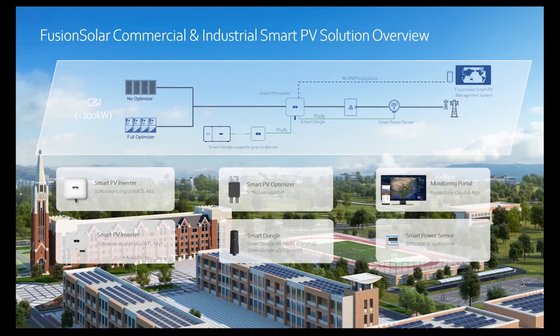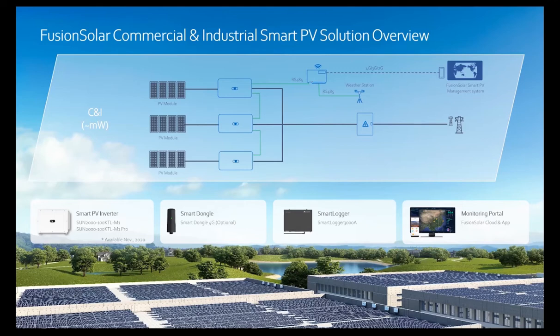So depending on the scale of the application, if it is a small scale, we are able to accommodate an inverter with a daisy chaining format with RS485 between the devices, or for larger applications, as you can see here on the megawatt plus scale, we then can accommodate with using our 100 KTL M1 inverter, which is a larger power class product. And typically for this type of application, most customers are going with the smart logger device, which is a data logger device able to accommodate not only just inverter data, but also external devices such as weather stations and also power meters as well, as shown on the overview diagram.